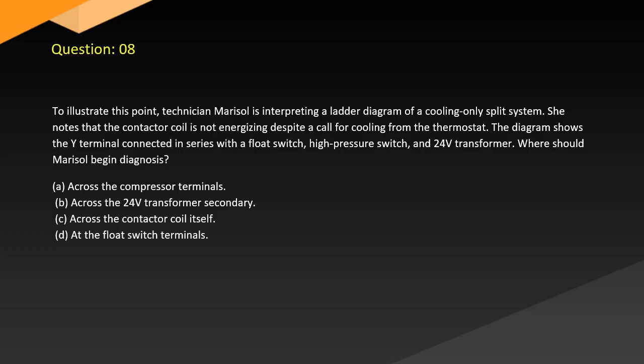Question 8. To illustrate this point, technician Marisol is interpreting a ladder diagram of a cooling-only split system. She notes that the contactor coil is not energizing despite a call for cooling from the thermostat. The diagram shows the Y terminal connected in series with a float switch, high-pressure switch, and 24V transformer. Where should Marisol begin diagnosis? A. Across the compressor terminals. B. Across the 24V transformer secondary. C. Across the contactor coil itself. D. At the float switch terminals.